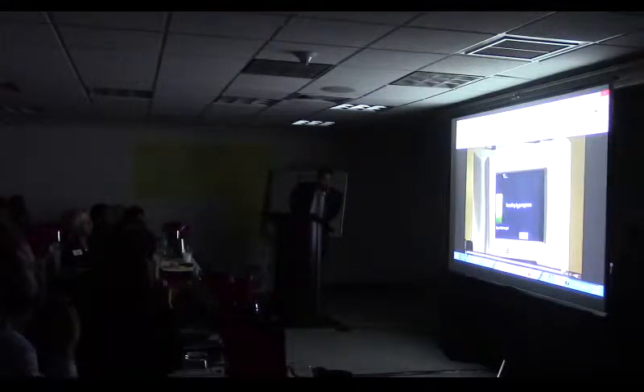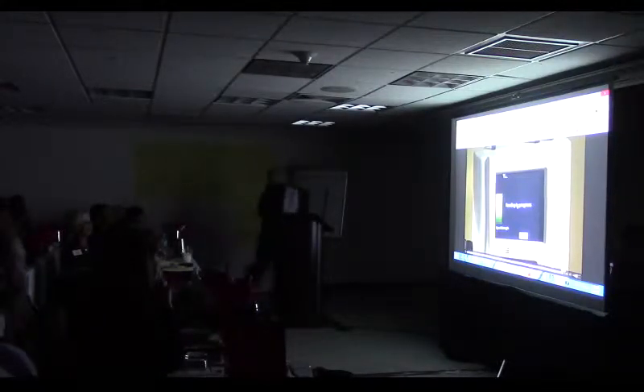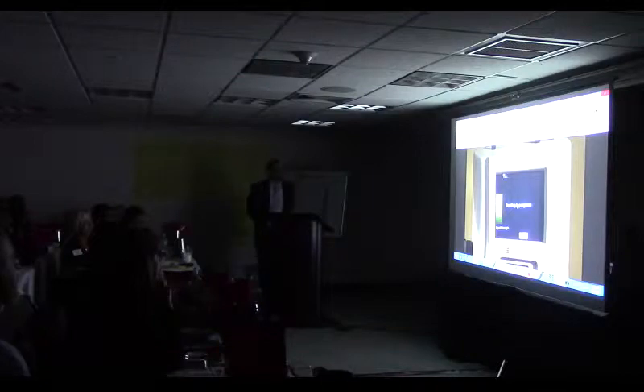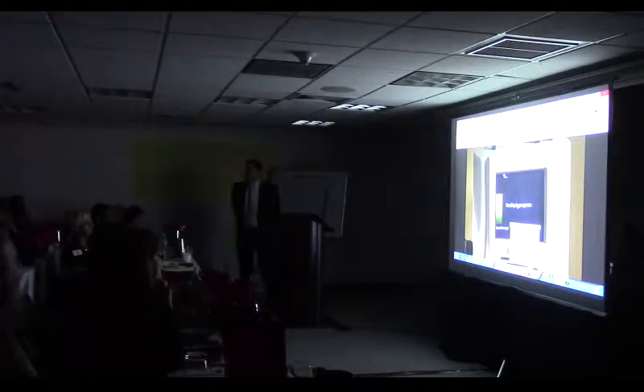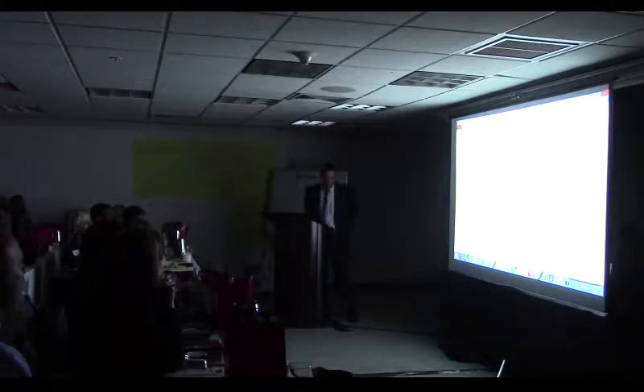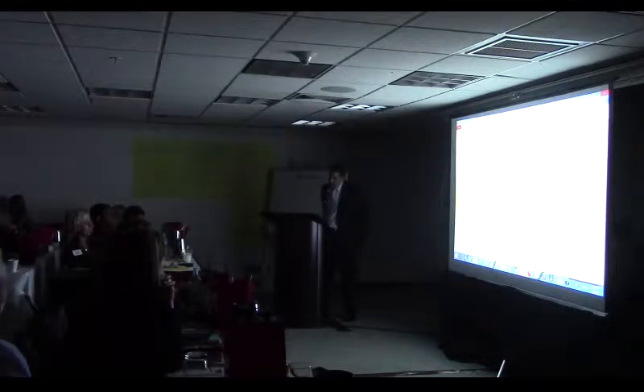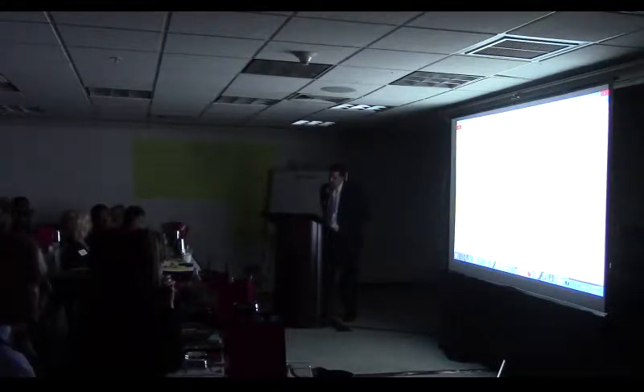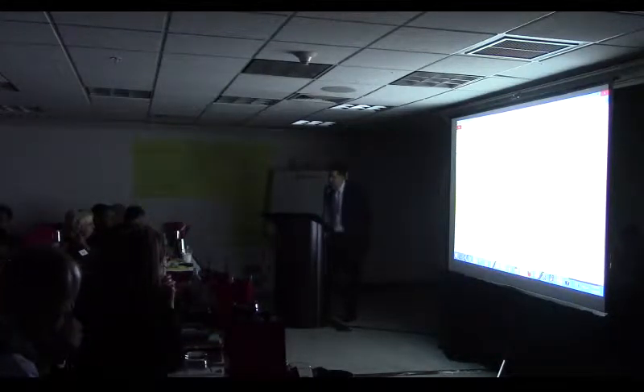The actual machine is much more reliable. That would be a kind of a disaster if that happened. We get the sensor and the equipment and all the educational material. That machine that you see is paired and calibrated to the sensor. That box is unique to the sensor. At the time of implant, and after the procedure, the box is calibrated at that point. Yes, the box is calibrated at implant, and the patient takes that home.